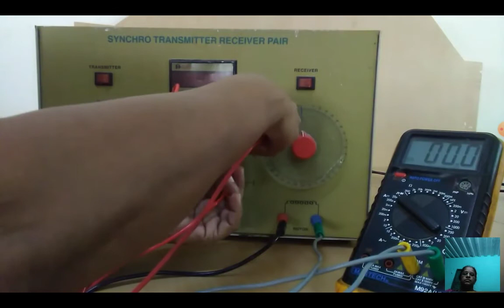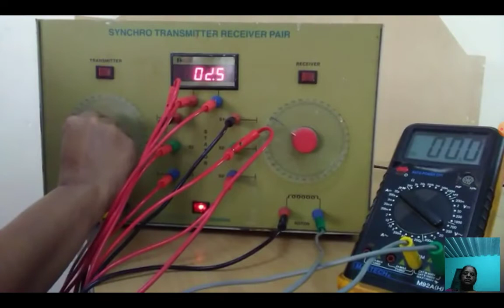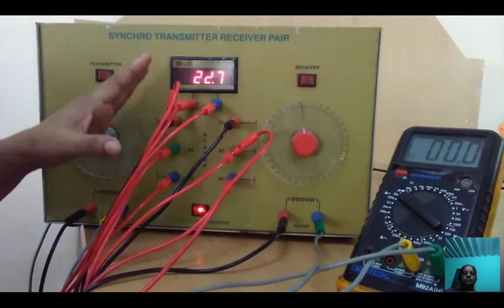At transmitter 0 degree, the receiver also reads 0. At 30 degree angular position of the transmitter, the receiver reads nearly 30 degree with some small error, and similarly at 60 degree and other values. Whatever angle we turn on the transmitter, we should get the same angle on the receiver side. We continue through 90, 150, 180, 210, 240, 270, 300, 330, and 360 degrees, noting down the transmitter angular position and the corresponding receiver angular position in degrees, then plot the graph.